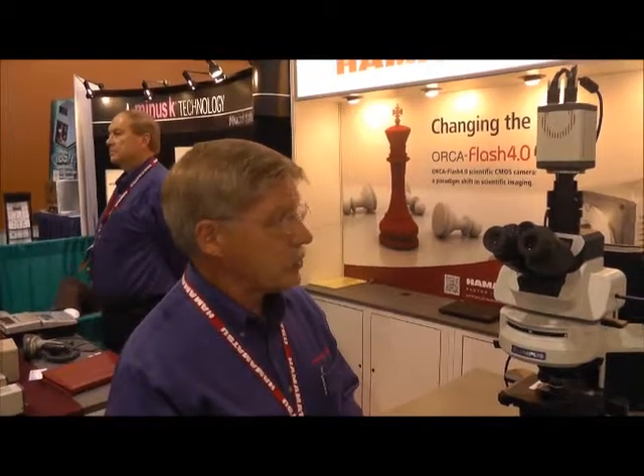This camera has a lot of new features. Basically, it's a CMOS camera instead of a CCD camera, which means we can have many more pixels that can be read out at a much faster frame rate with much lower read noise. For live cell biology, that means cell viability goes up, image content per image goes up, and the price goes down. It's a unique approach for people who have to go extremely fast with very delicate cells.